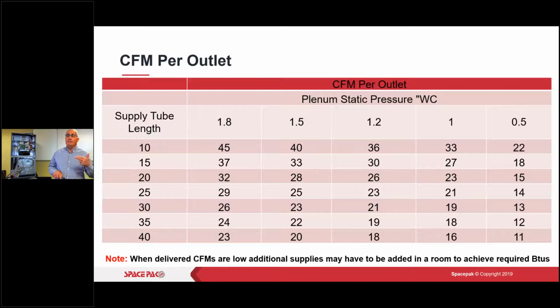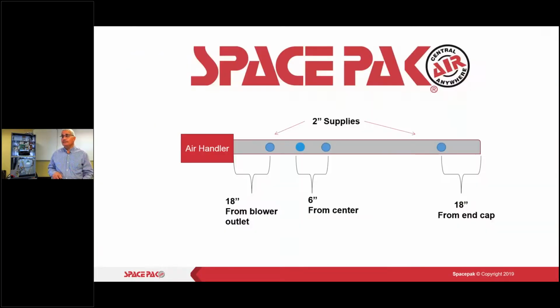All right, so based on the length of the tubing and the pressure in the plenum, we have charts like this available. You may want to take a screenshot of this if you don't have it. And it shows you, based on the length of the 2-inch drop and that static pressure, what my CFM is going to be. The longer those runs and as the pressure drops, you can see the CFM drops too. So when I'm delivering those low CFMs on longer runs, I'm going to need more drops.